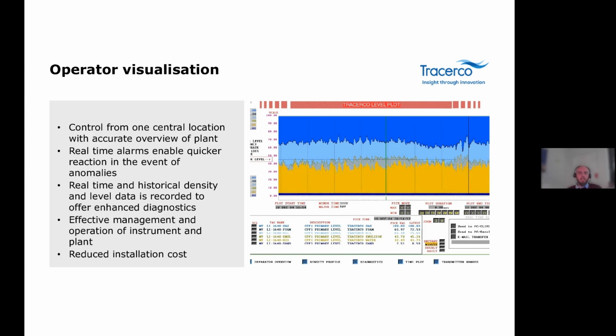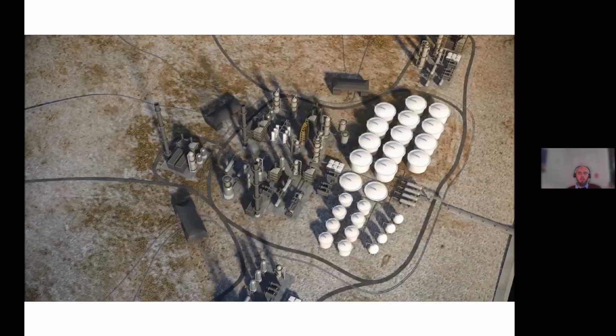Clients can use this information to aid in the vessel cleanout. One of our clients said that before installing the profiler, they would have to run the sand mud wash system on a number of occasions before a shutdown, and the cleanout would take around 3 days. Now they've got the visualization inside the vessel and can see the deposits in real time. They could increase the frequency of the jetting and reduce the cleanout time to only a few hours. In the next slide, we're going to look at a desalter operation and some of the typical challenges that can be seen.